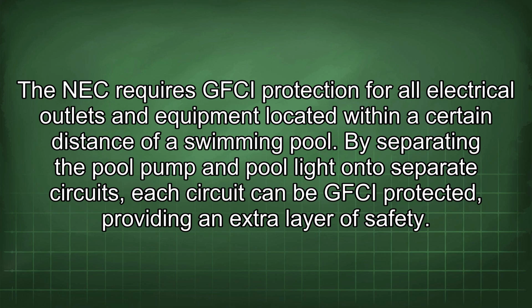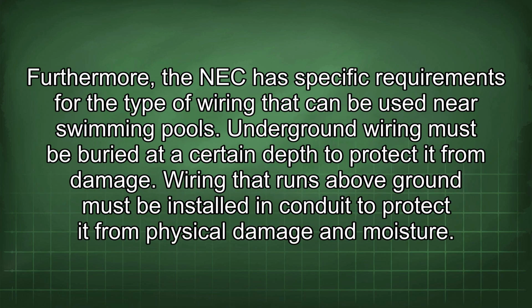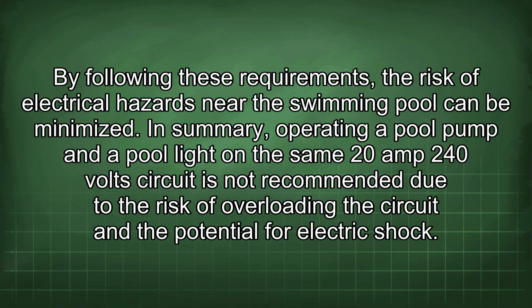Furthermore, the NEC has specific requirements for the type of wiring that can be used near swimming pools. Underground wiring must be buried at a certain depth to protect it from damage. Wiring that runs above ground must be installed in conduit to protect it from physical damage and moisture. By following these requirements, the risk of electrical hazards near the swimming pool can be minimized.